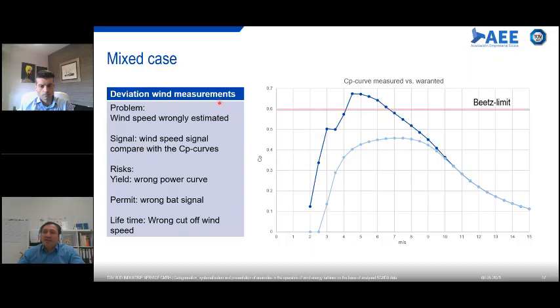So I'm calling this a mixed case example, because if my power curve is wrong, I have a wrong idea about the produced power output. But remember, the wind speed signal is also used to shut turbines off and on, for example for a bat signal — if we're above a certain wind speed we have to switch the turbine off or on, and therefore we could violate the permit. In the last case, as most turbines are still cut off using the anemometer at the top, when it's reaching the cut-out wind speed the turbine could be cut off too late. So a turbine which should cut off at 25 meters per second cutting off at maybe 26 meters per second could reduce its lifetime expectation.